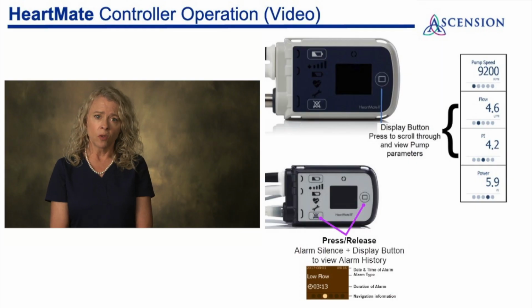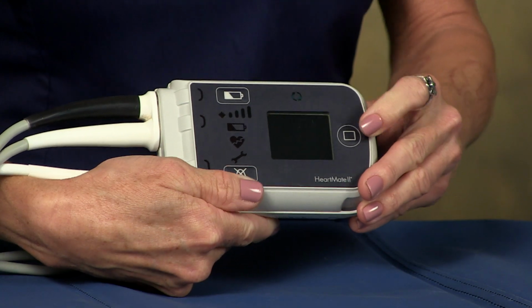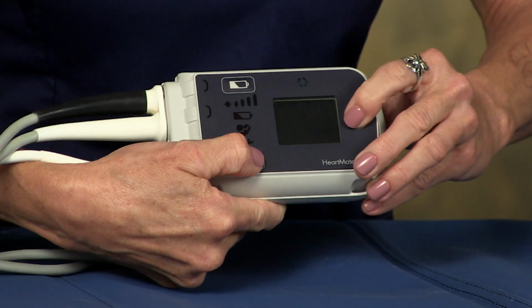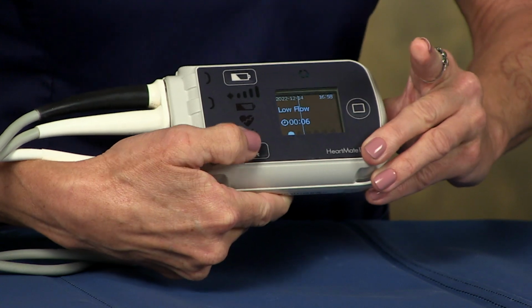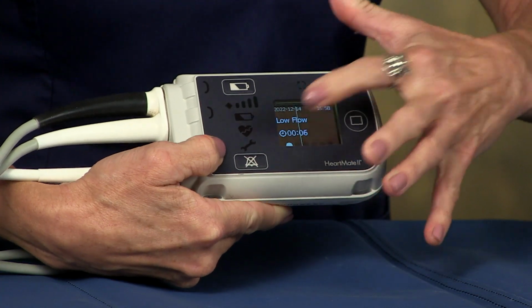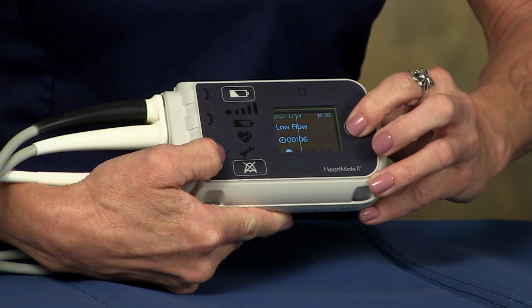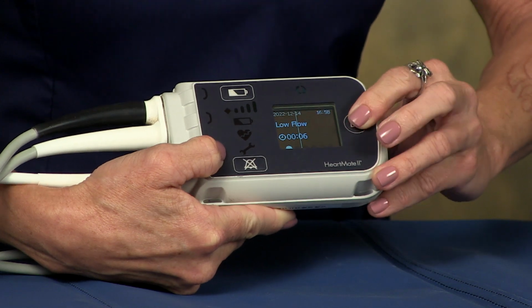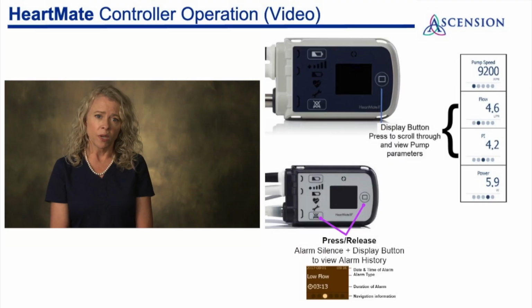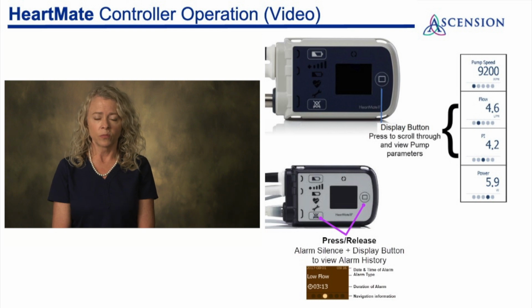Occasionally, an intermittent alarm occurs and you may not catch it, or the VAD coordinator may ask you to access the alarm history. To do this, you press and release, kind of fast, the display and silence buttons to open the alarm history screen. You'll see the alarm, a timestamp of when it occurred, and how long it lasted. Press the display button again to see additional alarms.